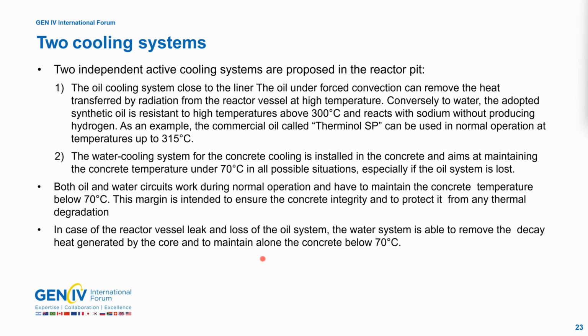After that we have a second cooling system, a little water cooling system inside the concrete in the external part. And this system can maintain the concrete temperature under 70 degrees in all the possible situations, even if the oil system is lost. Both systems are working during normal operation to maintain the concrete at low temperature. And in case of a reactor vessel leak and the loss of the oil system, the water system is able to remove alone the decay heat generated by the core and to maintain the concrete below 70 degrees.